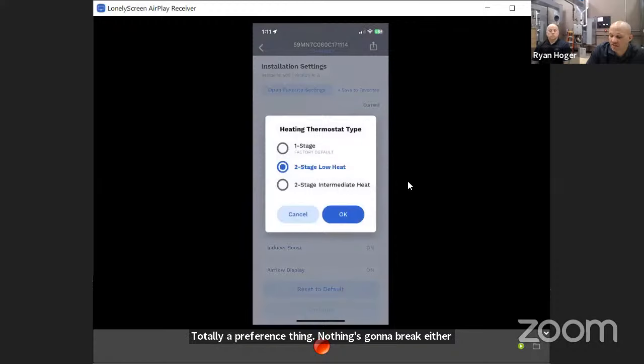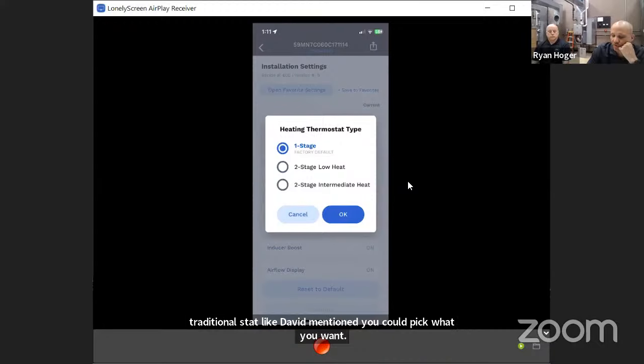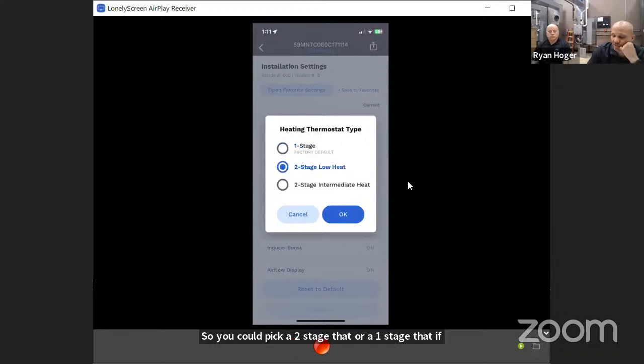Heat thermostat staging. You could pick by default a single stage stat. Obviously, if you have an Infinity Evolution stat, that takes priority. It'll override these. But if you're going to wire a traditional stat, like David mentioned, you could pick what you want. So you could pick a 2-stage stat or a 1-stage stat. If you pick a 2-stage stat, you could pick what first stage means. Does it mean you're running the lowest heat possible, or does it mean you're running medium heat? So basically like 40% or like 65% of gas flow. Ish.